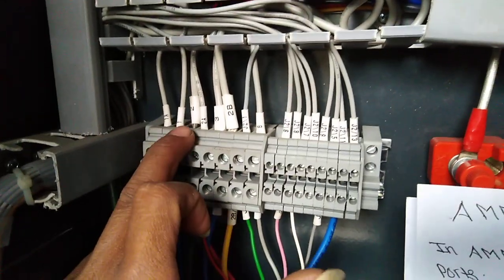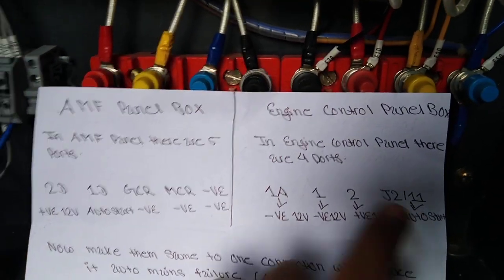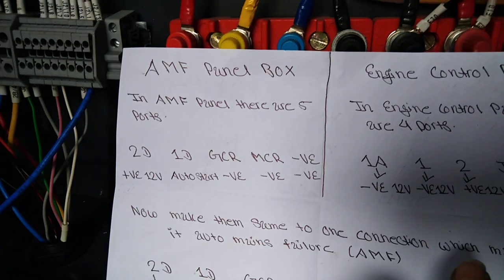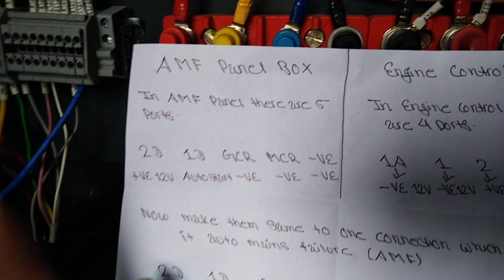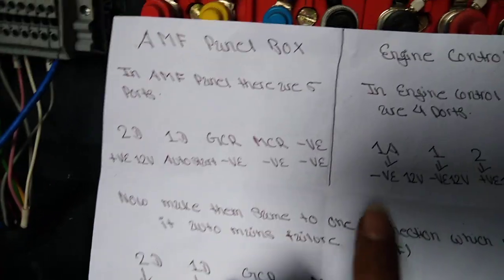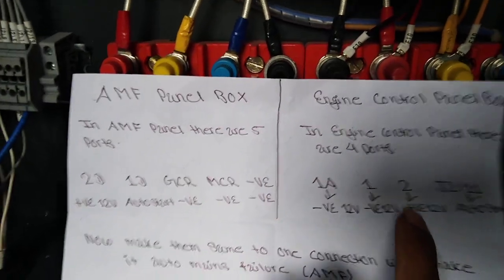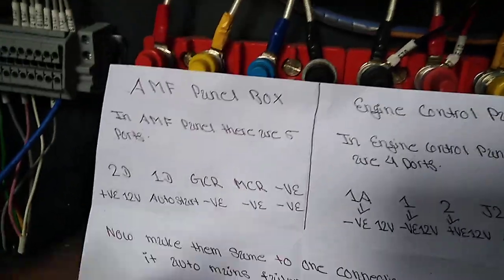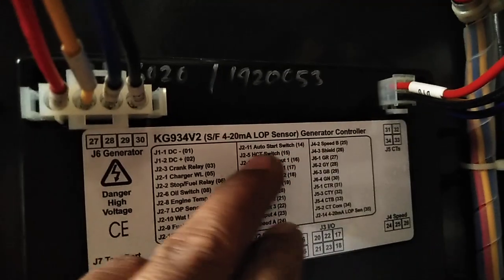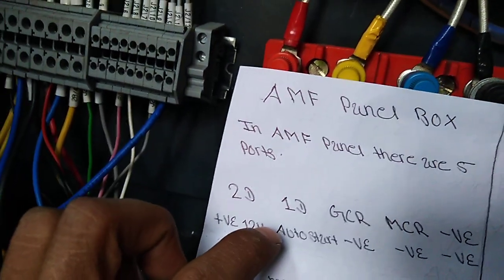You can see here ports 1A, 1, 2, and J2/11. We order them in serial wise. 2D means positive — 12 volt — so you connect this into port number 2 of the genset. After that, 1D is auto start. You can also see here J2/11 is the auto start switch, so we connect auto start into J2/11.